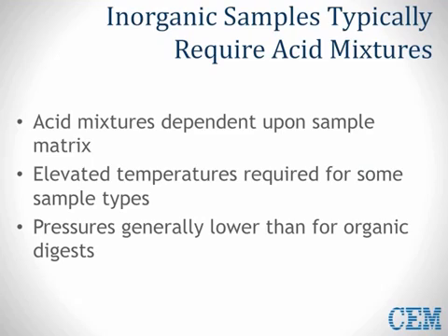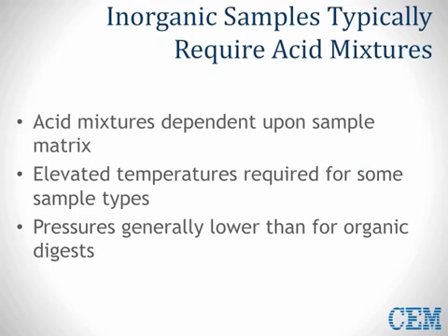Inorganic samples are more complex and will require different acid mixtures in order to provide a completely digested sample. Some inorganic materials will require temperatures as high as 300 degrees Celsius in order to get a total digest. Inorganic digestion is more complicated than organic; fortunately, application notes have been developed to cover the vast majority of these cases.